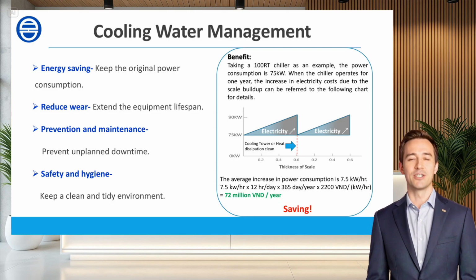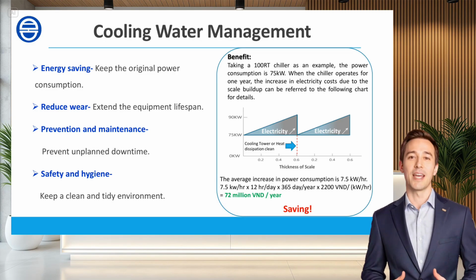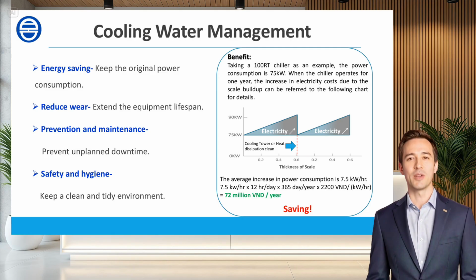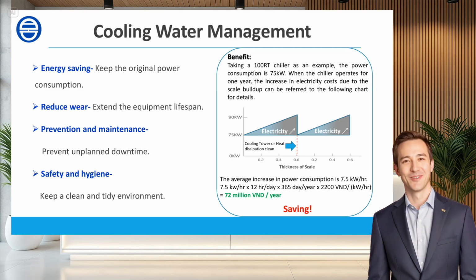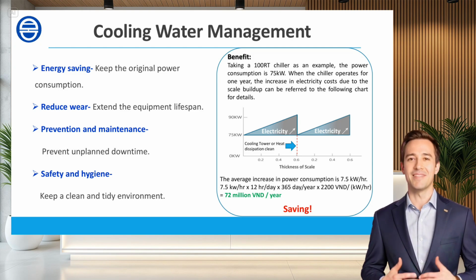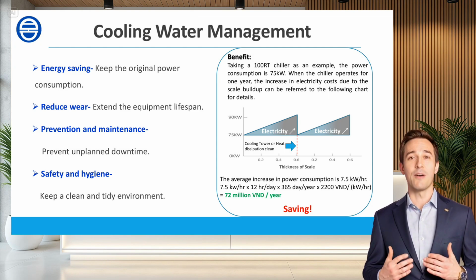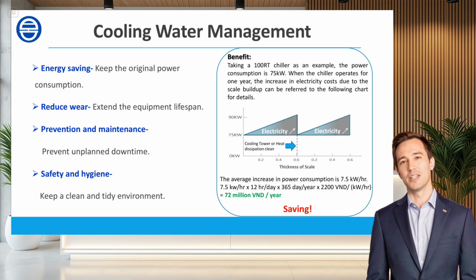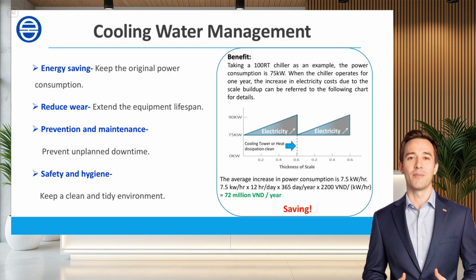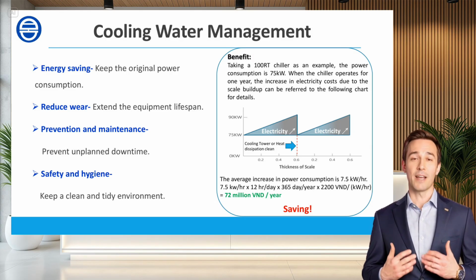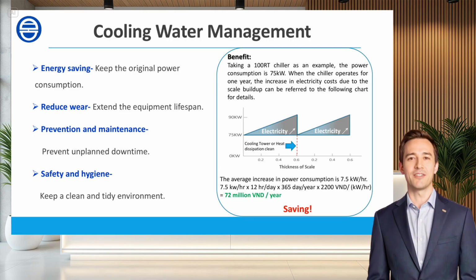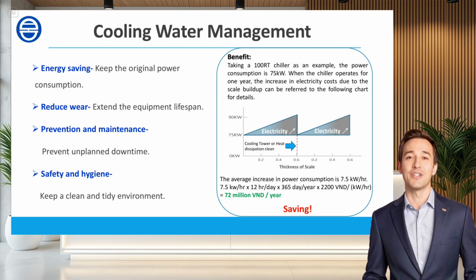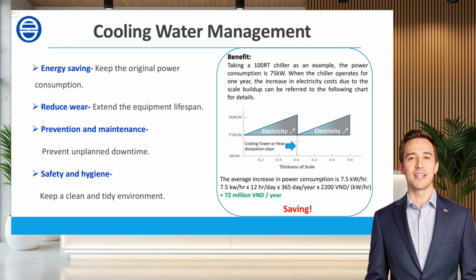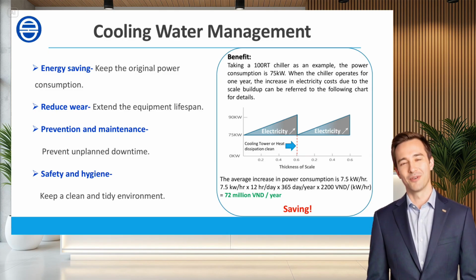Let's take a 100-ton chiller that runs at 75 kilowatt for a whole year as an example. From this chart, you can see that as the system operates and the cooling water gets more concentrated, scale gradually builds up inside the equipment. As that scale layer gets thicker, say around 0.6 millimeter, the power consumption climbs to 90 kilowatt. At that point, the chiller is under heavy load, triggering alarms. In some cases, it might even shut down unexpectedly. That's when the engineering or maintenance team rushes in to do an acid cleaning on the condenser. After cleaning, power consumption drops back to 75 kilowatt.